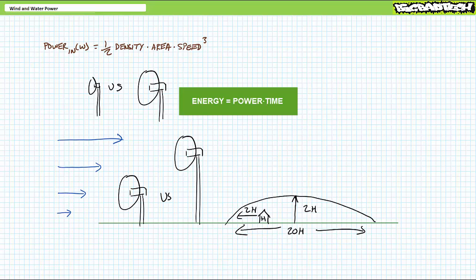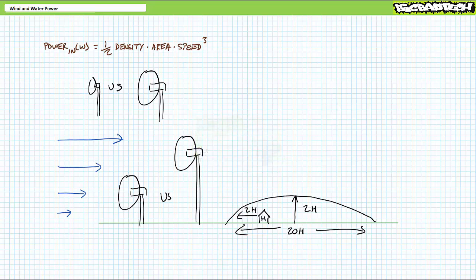This means a turbine installed in a low wind environment that regularly experiences low wind on a nearly continuous basis, even if it's at the low end of the operational range of a particular turbine, might actually produce more energy than would a single larger, more powerful turbine operated at the rated speed only on occasion. I'm of course referring to capacity factor, which is the percent a turbine runs at capacity versus sitting idle waiting for something to happen. For this reason, there's often a lengthy wind speed data collection and analysis period prior to installing a turbine to see if it's worth the expense of doing so.